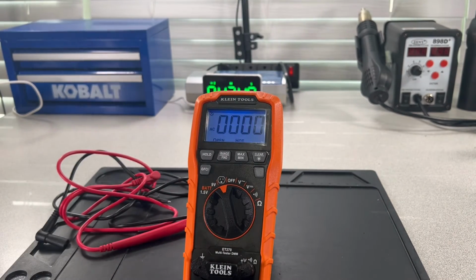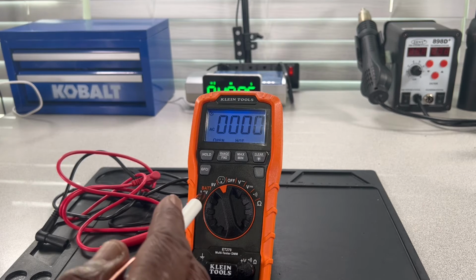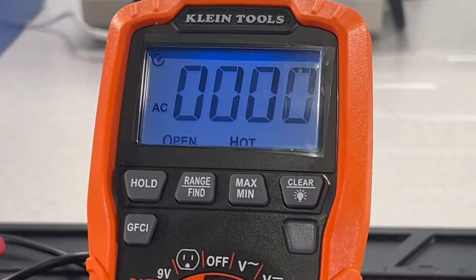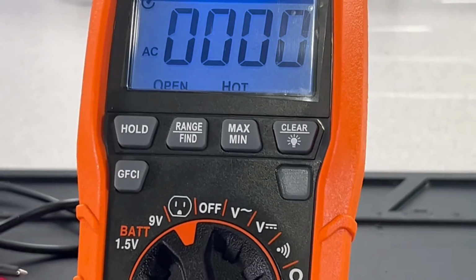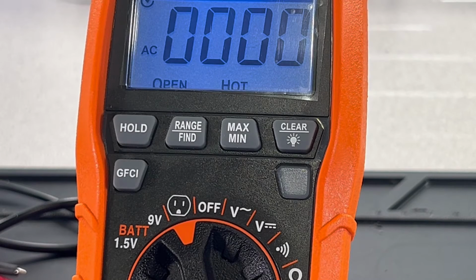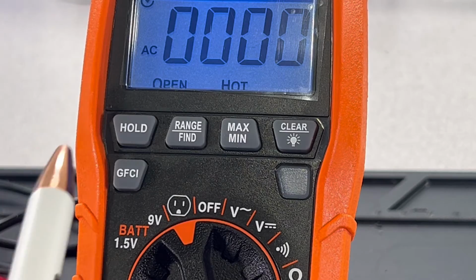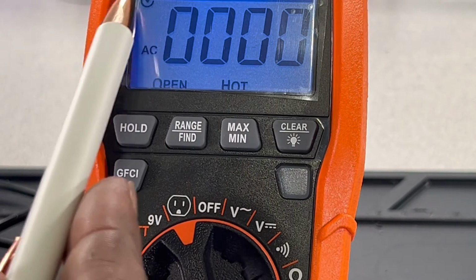Now, there are some other things I want to share with you, and then we'll go into some of the testing. Let me call out some of the features this meter has. They say it has an auto power off indicator, a data hold indicator, which would be the hold button, an automatic ranging indicator, a GFCI indicator, and a battery test indicator, that would be those two. Let me get you closer. A battery test indicator, the maximum value indicator, that would be the min-max, the minimum value indicator, audible continuity, that would be that, and a low battery indicator, I think it's up there.